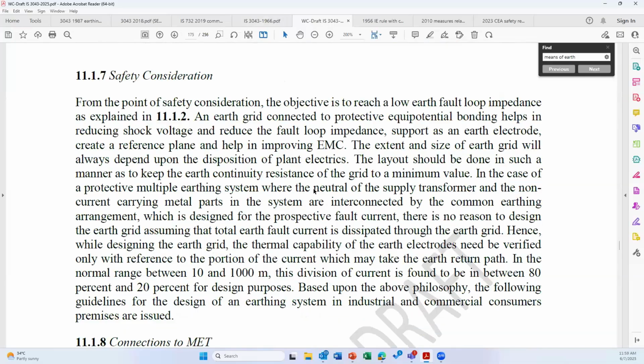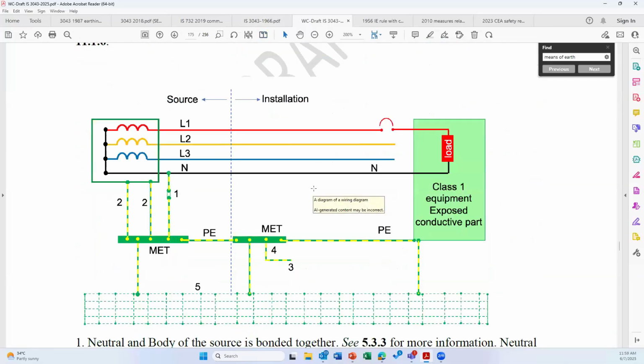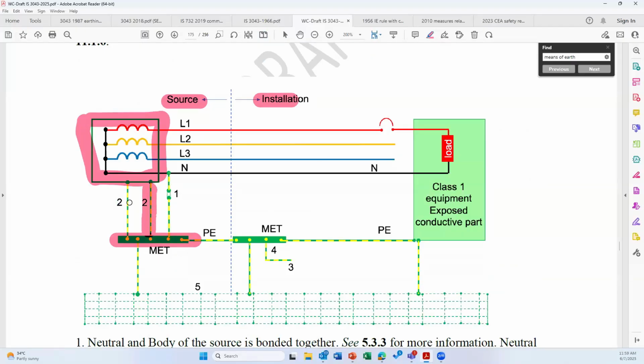Clause number 11, examples of typical building. Please note that these figures are not invented by the committee as new. These were already existing. This is the typical method of earthing if you have a transformer. You see, you have the source, you have the installation, you have the transformer. You have a MET, a common bus bar. Body of the transformer is connected to the MET, maybe two connections. Neutral of the transformer is connected to the MET. Then you have the PE conductor, which goes to the exposed conductive parts of your installation.